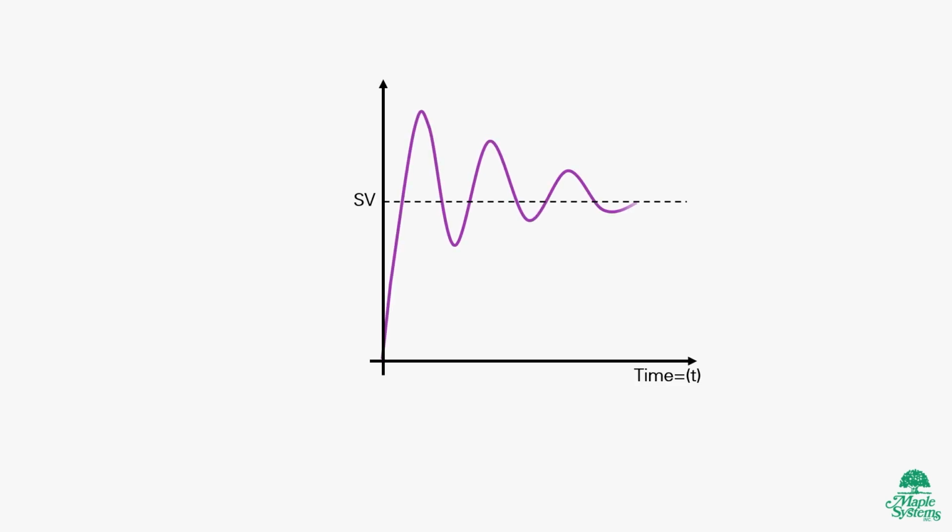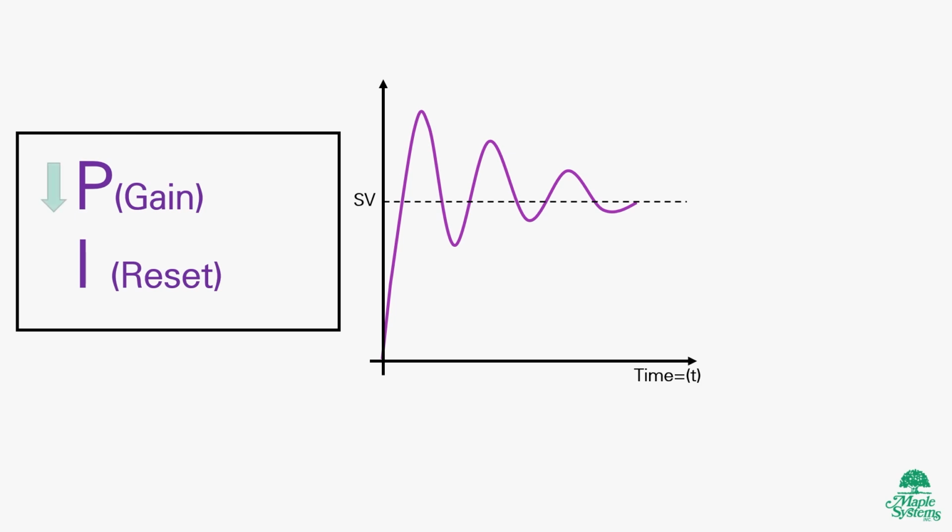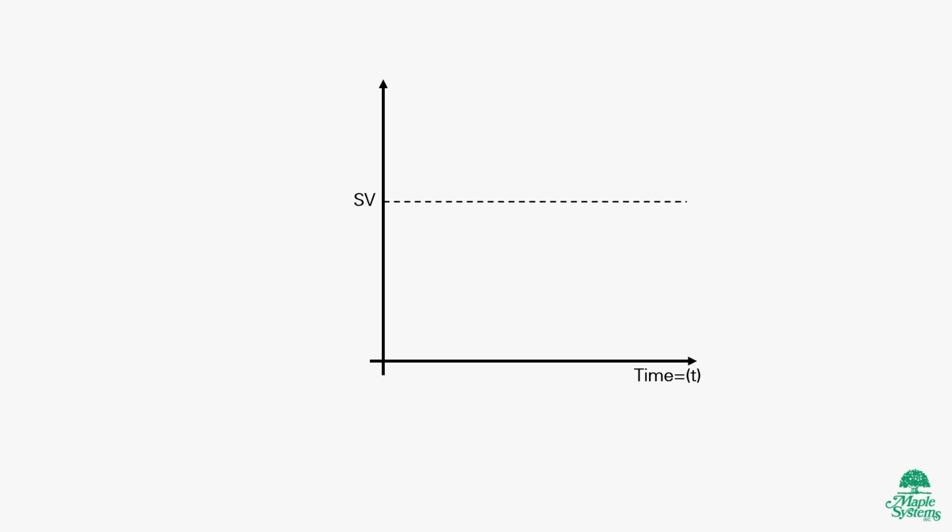So if your process variable changes quickly and changes to the control variable, you will start with a low gain, possibly as low as 0.1, while adjusting your reset to 1 in 10 repeats per minute. Conversely, if the process variable changes slowly, start with higher gains and lower reset. The proportional gain will be between 2 and 8, and 0.05 and 0.5 for the reset, making sure to only adjust the parameters one at a time. Continue this pattern until you have achieved a stable process.